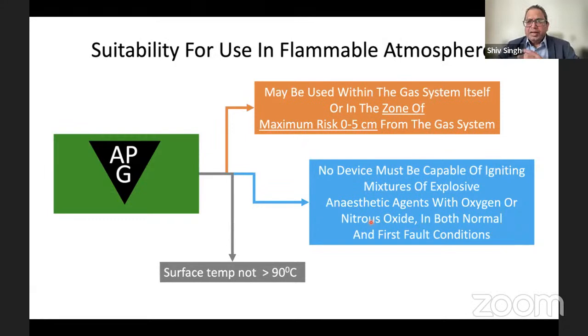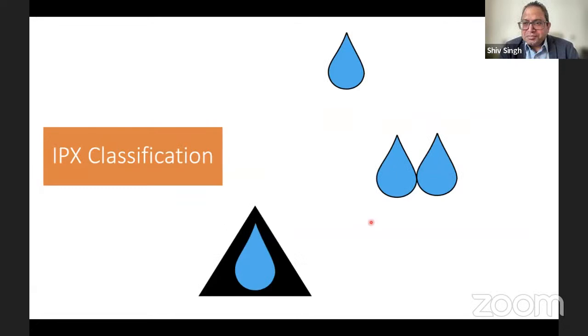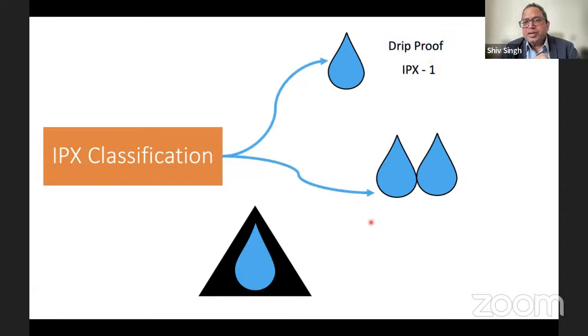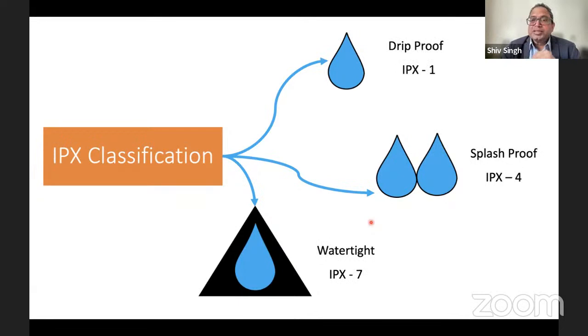Now, if you look at equipment, where do you clamp your pumps? On the pole. And what do you have above that? You have a bag of saline, Hartmann's, Plasma-Lyte, whatever. And it could be dripping into the pumps, your infusion pumps or your TIVA pumps. So equipment which can be exposed to water needs to also have an IPX classification. IPX stands for ingress protection, so protection against ingress of water. If you see a droplet, it is drip proof, IPX1. If you see two droplets on the box, it is splash proof, or IPX4. But if you see equipment with a droplet with a triangle in it, that is IPX7, or watertight. That means you can actually dunk it into a bucket of water and bring it out, and nothing will happen to it. So it is highly protective against ingress of water. This is another classification you need to know.